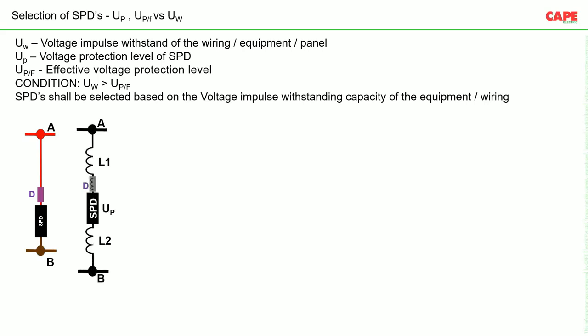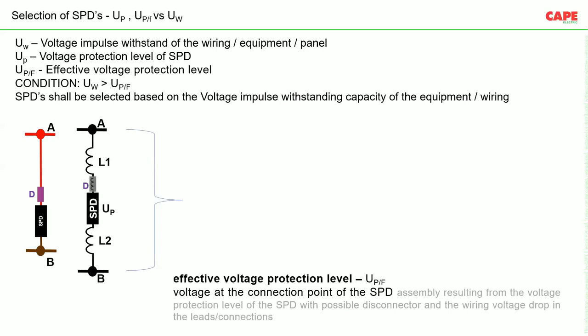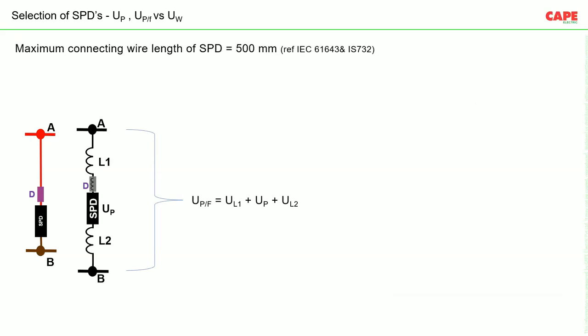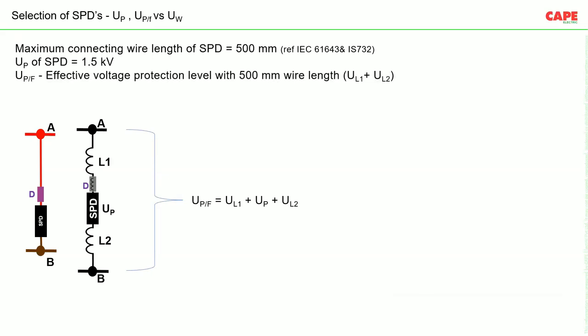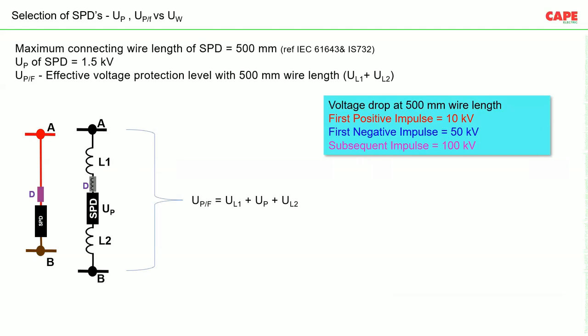So let's see, this is an SPD connected in between point A and B, and D is a backup protection or disconnector fuse. L1 is the wire length 1. Then UP is the voltage protection level of the SPD. Then L2. Now, the effective voltage protection level, UPF, will be the voltage drop across L1 plus UP plus the voltage drop across L2. If we go as per standard IS 732 and IEC 61643, we have considered a wire length of 500 mm, and let us calculate the effective voltage protection level.